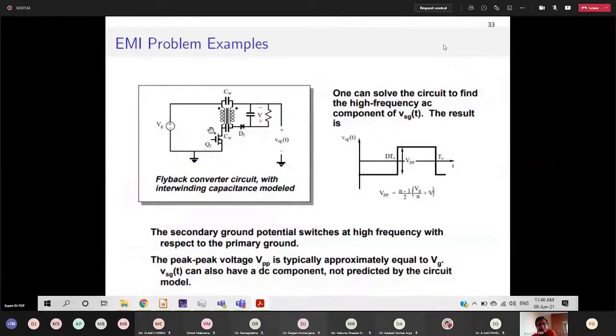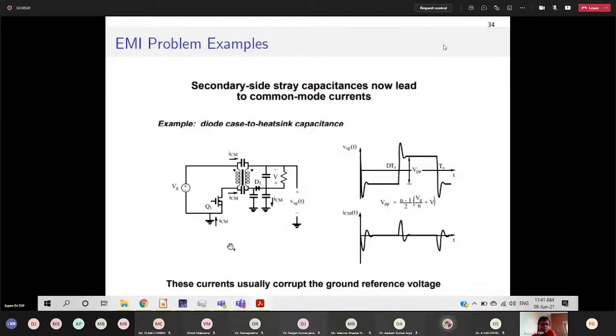With every dV by dt here, there will definitely be a stray capacitance. That stray capacitance would inject some current into this ground. So even though we don't want any interaction between this and this, because of this common mode voltage, you are injecting some current into the other ground, and that may impact the other circuits also. You can add a common mode filter separately, or since this is happening within this single topology itself, this is just showing you those current waveforms, the common mode current going between this and this. And this is something that you miss in the analysis, because for common mode analysis, you need to really be aware that you are doing a common mode analysis and start doing it. Otherwise, you will not see these currents.